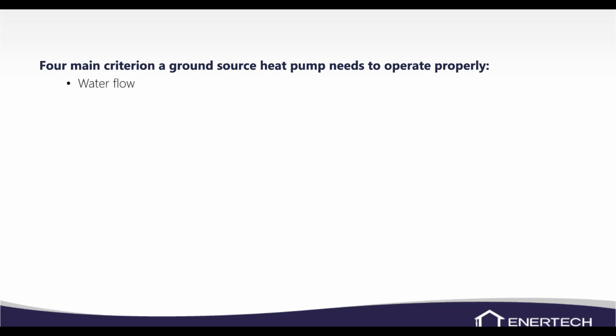Basically, we've got to have water flow for the heat pump to operate properly. Whenever you call tech support, a lot of times that's what we'll ask you first: water flow. We've got to have water flow or the unit won't operate properly. So we've got to make sure our pumps are working. And if you've got a water to water unit, then you've got water flow on both sides, the load and the source. So you've got to make sure that we've got water flow on both sides. You've got to have a proper energy source or energy dump. So your loop field needs to be sized properly.